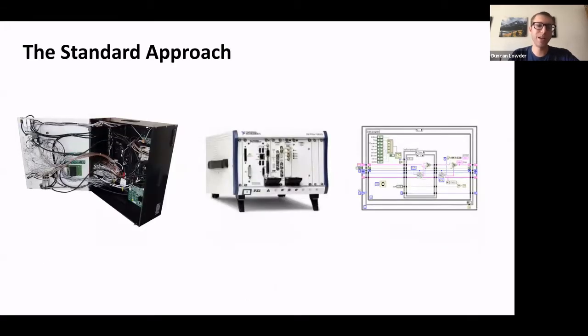The standardized functional test fixture approach uses a bed of nails fixture that's manually wired, typically from the test probe to either an interface plate or the actual instrumentation. Most common is a rack of PXI test equipment, fairly expensive, purchased from vendors like National Instruments or Keysight. Most people use a combination of LabVIEW and TestStand to develop and run the test scripts in the factory.